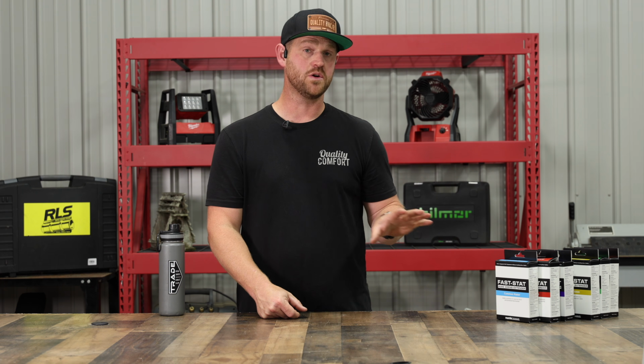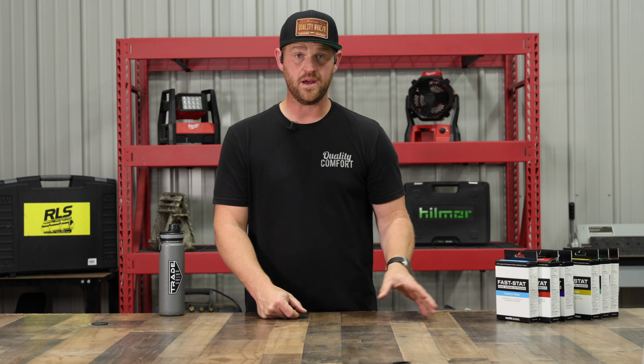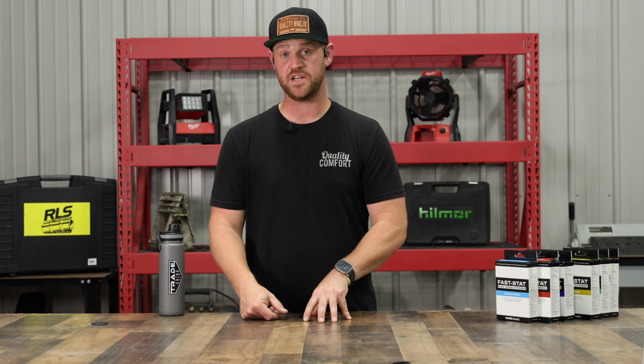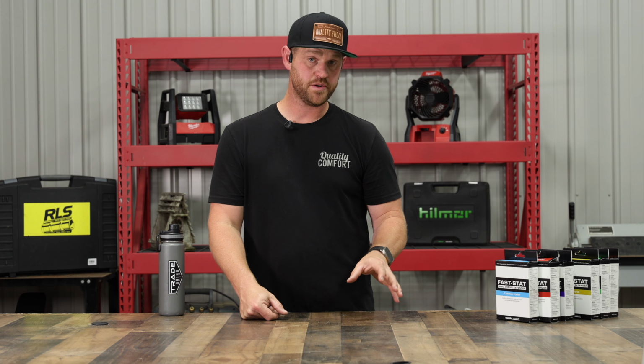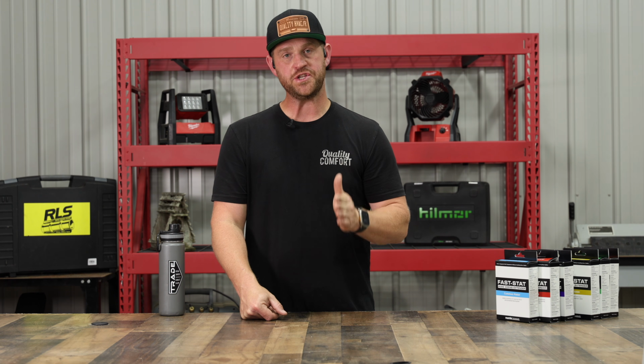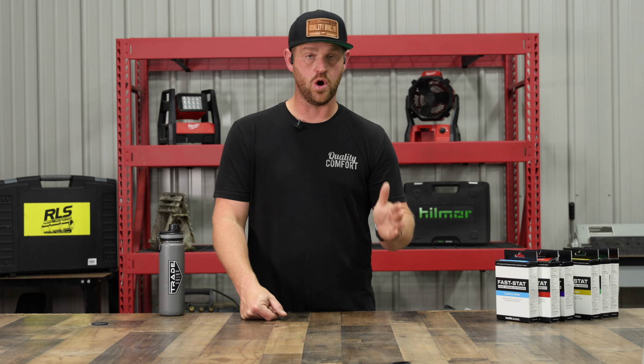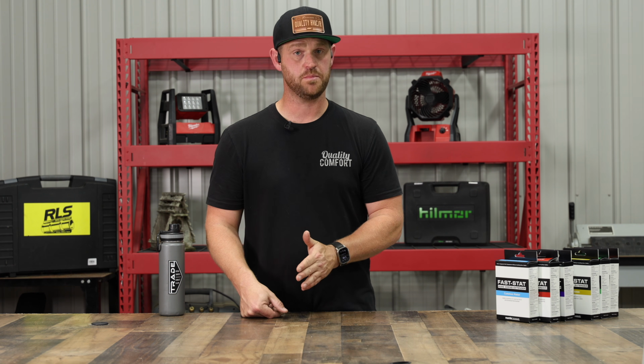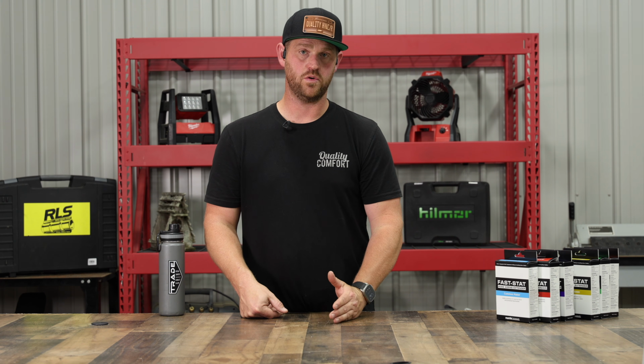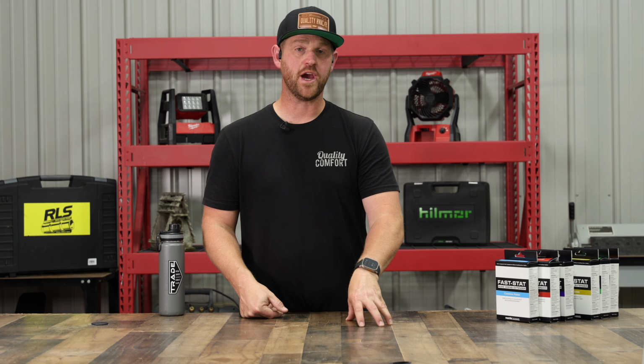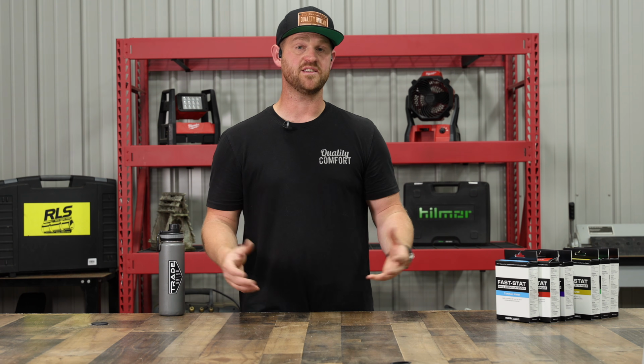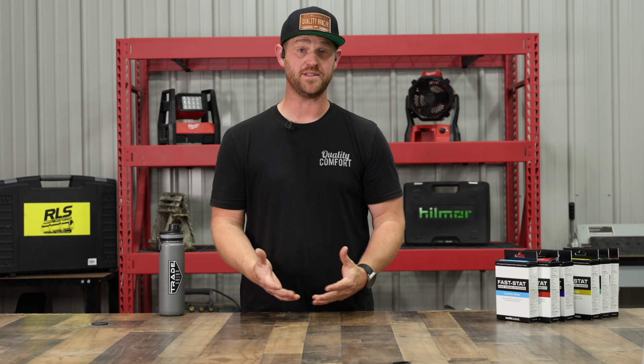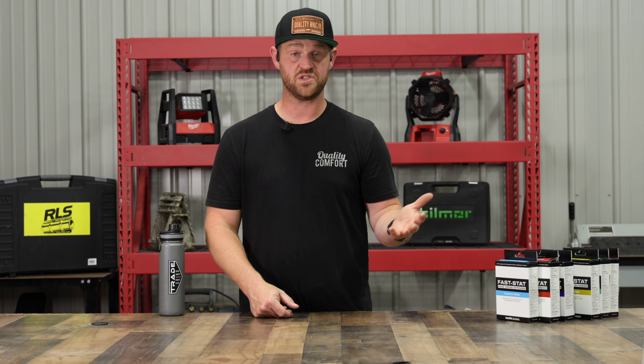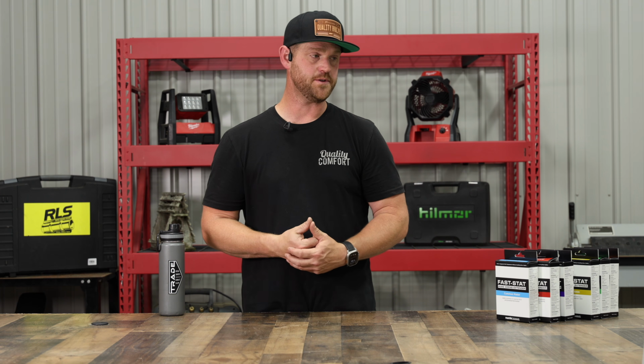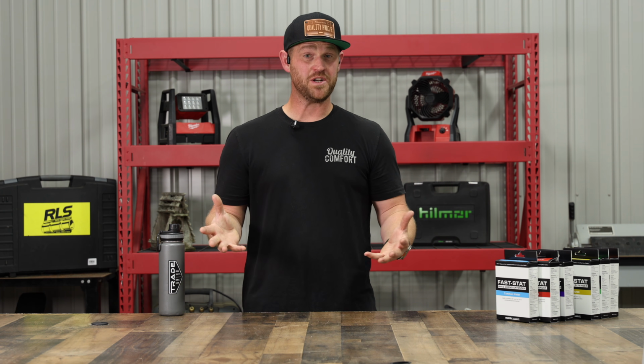And that really goes across the board for all equipment. I mean, just because you can get single stage equipment with ECM motors. So I think it's just a good habit to fall into where every change out that you're going to do an estimate on, if it's possible, go ahead and do a static pressure reading. Look at the return sizes. Make sure everything is adequate for your new system so there's no surprises when you're actually on the install and the guys are there doing the work. So, but that's pretty much it in a nutshell.